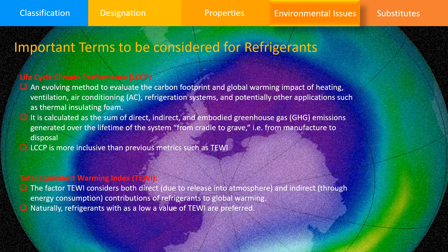The Montreal Protocol has already resulted in phasing out of R11 and R12, replaced by R22. But at present different substitutes are available. The HCFC refrigerant R123, that is CF3CHCl2, in place of R11. The refrigerants R134A and R152A in place of R12. Then there are 143A and 125 in place of R502, which is an azeotropic mixture. The hydrocarbon refrigerants pure propane, that is R290, and isobutane R600A may also be used in place of R12. The only problem is they are highly flammable.